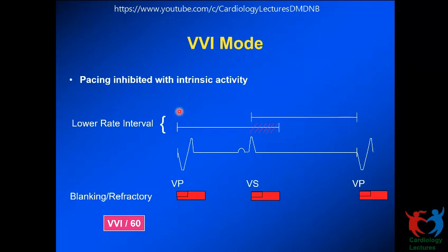In a VVI, if you're programming a rate of 60 beats per minute, we deliver a pacing pulse, start the refractory and blanking that we have programmed, and the clock runs for 1000 milliseconds. It sees an intrinsic ventricular event. This is called a V sense by the pacemaker, well outside the refractory, and it resets the clock. It also starts a refractory and blanking, and at the end of the lower rate interval, it delivers a V pace, starts another refractory and blanking, and begins another lower rate interval. That's how the VVI or the AAI runs.